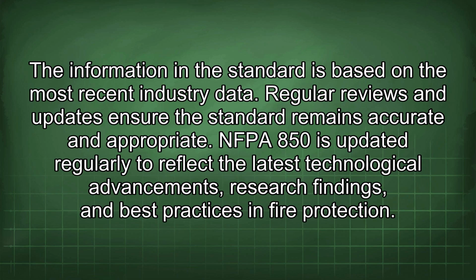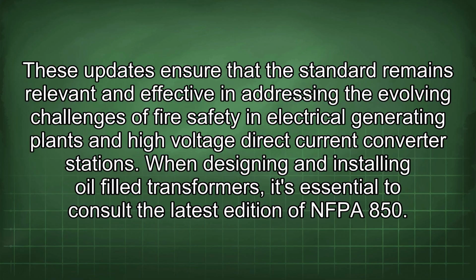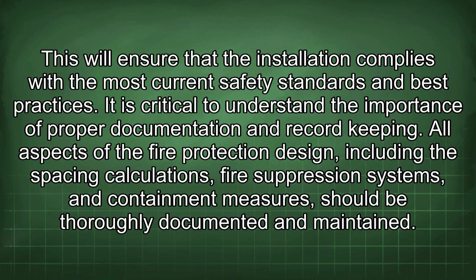NFPA 850 is updated regularly to reflect the latest technological advancements, research findings, and best practices in fire protection. These updates ensure that the standard remains relevant and effective in addressing the evolving challenges of fire safety in electrical generating plants and high-voltage direct current converter stations. When designing and installing oil-filled transformers, it's essential to consult the latest edition of NFPA 850. This will ensure that the installation complies with the most current safety standards and best practices.